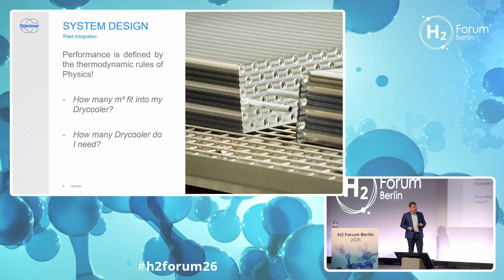That needs to be kept in mind, because the next point is sound. Sound is generated by moving air and rotating equipment. On the cooling plant, the only sound-emitting element is the fan — not the cooler itself, not the electrolyzer. It's really about how many fans are running on the cooler, and that tells me how much air I have to move on a large-scale plant — we're talking about 100,000 cubic meters per unit.